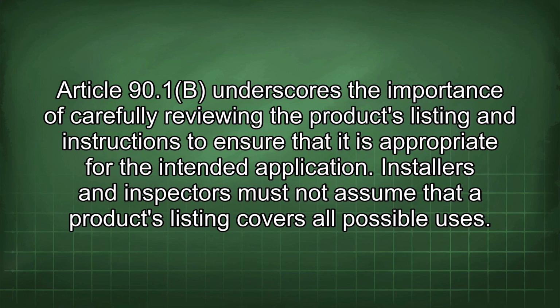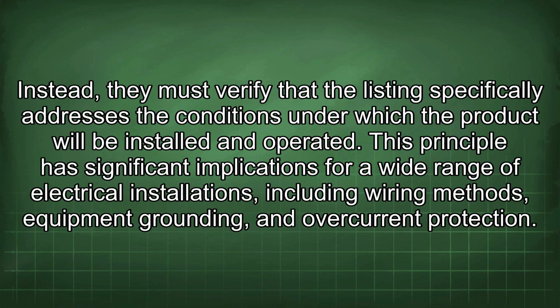Installers and inspectors must not assume that a product's listing covers all possible uses. Instead, they must verify that the listing specifically addresses the conditions under which the product will be installed and operated. This principle has significant implications for a wide range of electrical installations, including wiring methods, equipment grounding, and overcurrent protection.